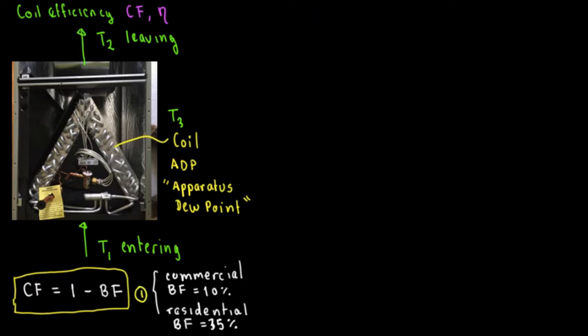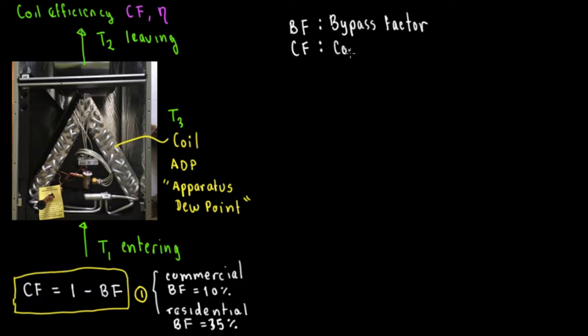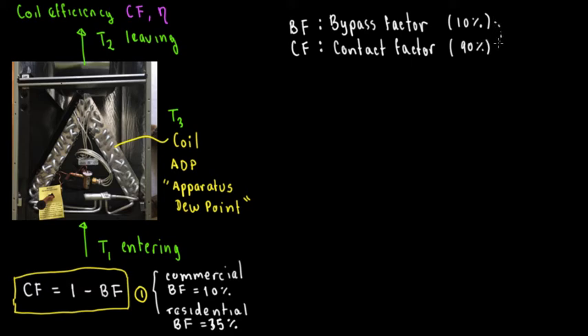Formula number 2 is related to the bypass factor. So, bypass factor BF measures how inefficient the coil is, and contact factor CF measures how efficient it is. For example, if the coil has a 10% bypass factor, that means 10% of the air is not in contact with the coil, so the contact factor is going to be 90%.